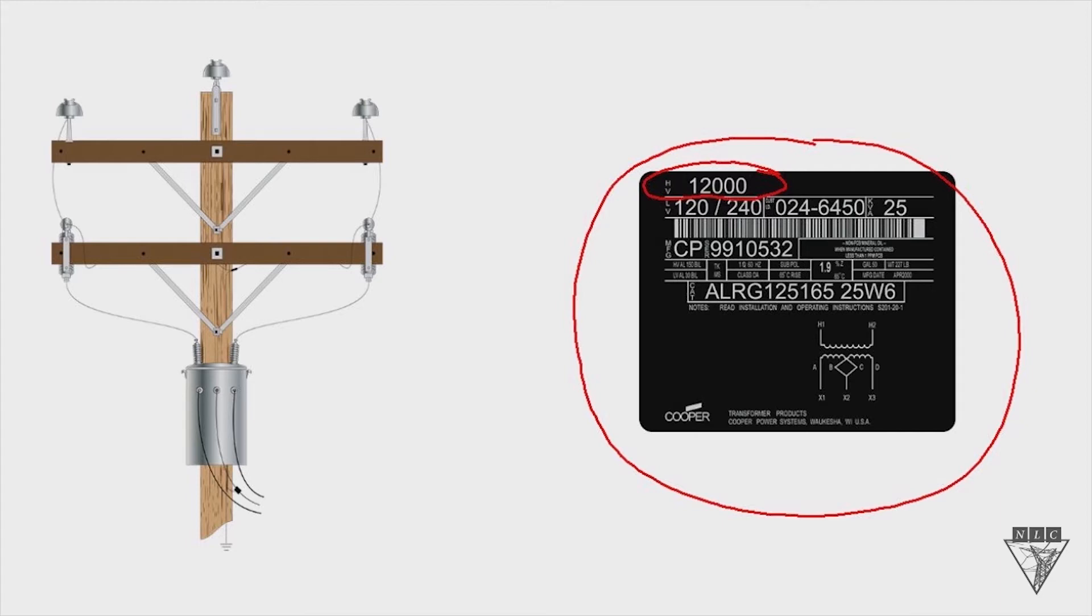If there's only one number on the high voltage rating, then it's going to be a phase-to-phase connection. So over here on the left on our structure, it would be a phase-to-phase connection, and you would need it to have 12,000 volts in order to get the proper secondary voltage out of your transformer.